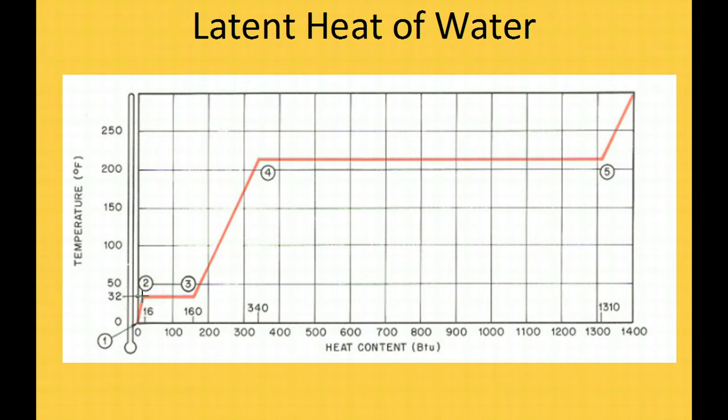Once that ice reaches 32 degrees and more heat is added, the temperature remains at 32 degrees from point 2 to point 3. This is where it's changing state from a block of ice into a puddle of water. If you look here, it absorbs about 144 BTUs of heat for that block of ice to change state from solid to liquid. You can see it takes quite a bit more energy from point 2 to point 3 than it does from point 1 to point 2.